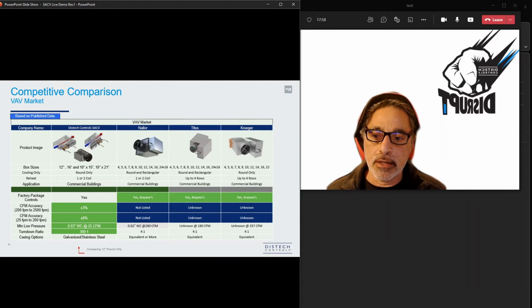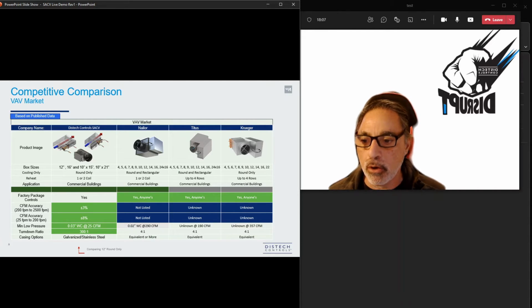We are looking at around plus or minus 3% accuracy at 200 FPM to 2500 FPM. When you go below that, to around 25 FPM to 200 FPM, we're at plus or minus 8%. And we're talking about minimum low pressures of 0.03 inches at 25 CFM.